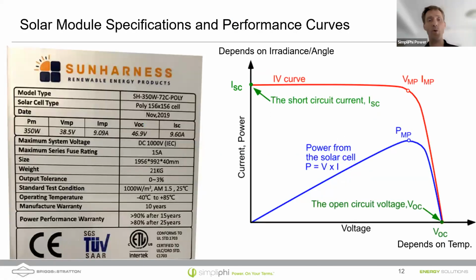Great, okay, so I wanted to point out for you on the back of a solar panel - this is a typical module, a sun harness label on a solar panel that I just grabbed offline. The standard test conditions are about 1,000 watts per meter squared with an AM 1.5, meaning air mass 1.5, so it goes through 1.5 atmospheres. That's become the standard because it's about the amount of atmosphere sunlight goes through when it hits the northern hemisphere, where the testing was being done.